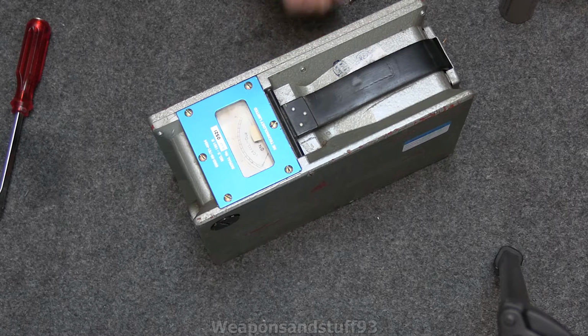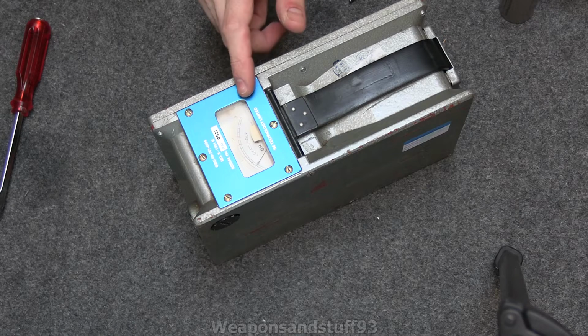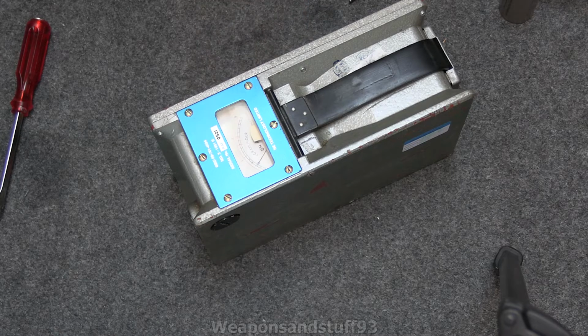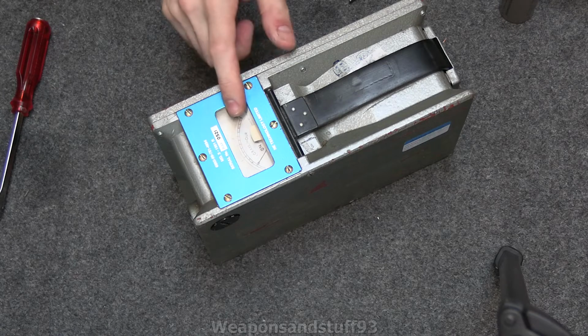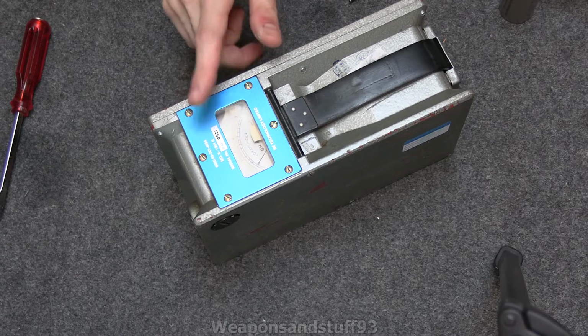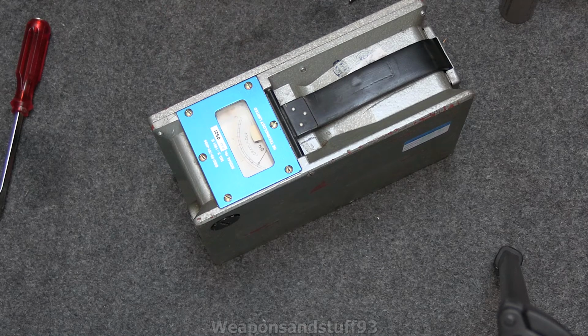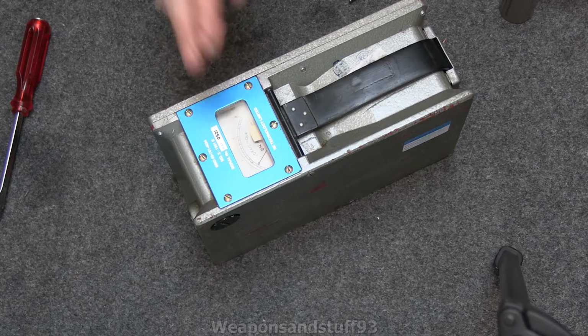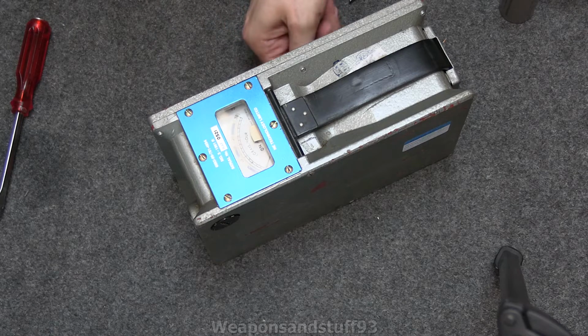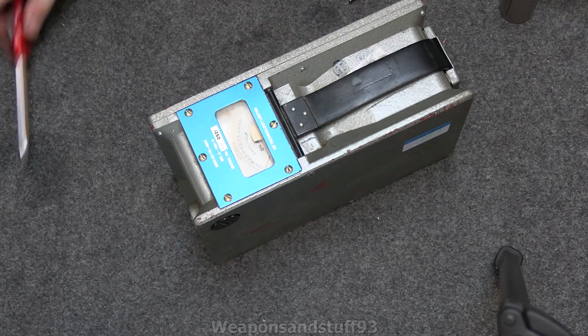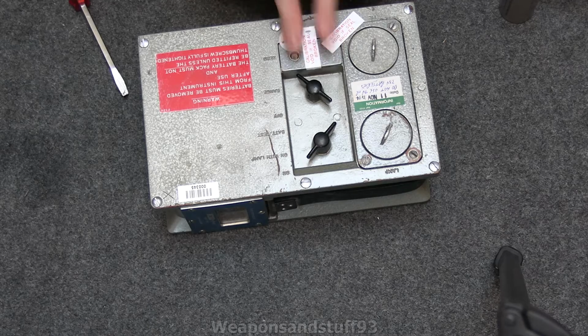Now what we'll do, we'll turn it on and see what sort of reading we get. Now actually that's pretty good. The problem is with a lot of these, if you turn these on and they've not been used in ages, there's too much moisture in them. So you can get really weird readings on this. But I'm going to show you anyway what you would do even if the needle had gone crazy. What we're going to do is go to set 0, and we're going to set the 0. Now, the 0 and the calibration controls are under there. So actually what I'll do is I'll show you how to change the silica gel in it first, and then we'll go on to doing that there.